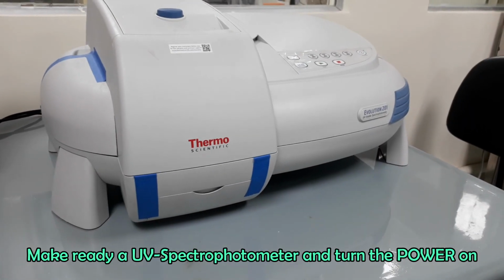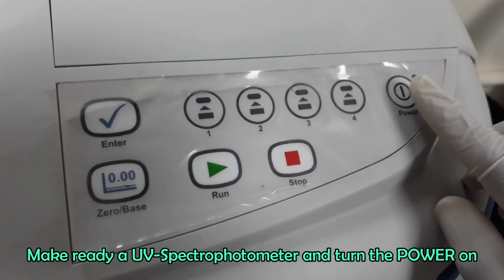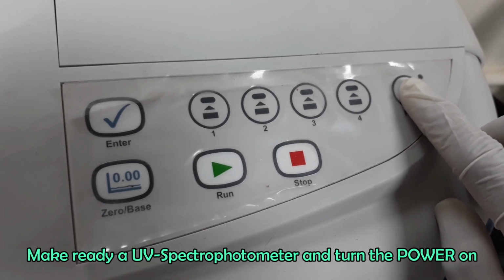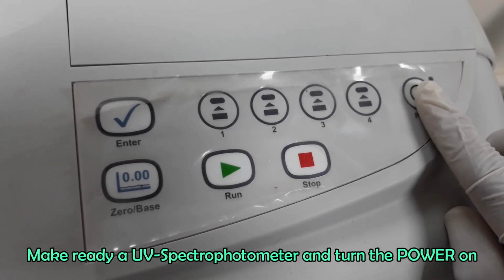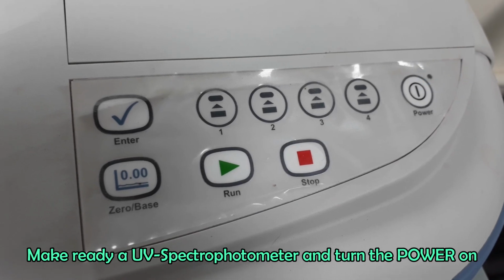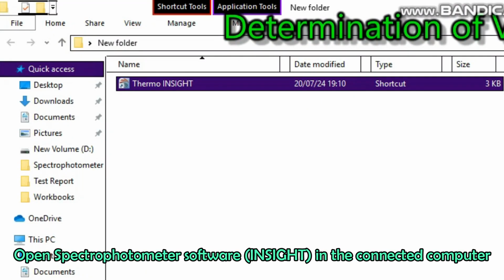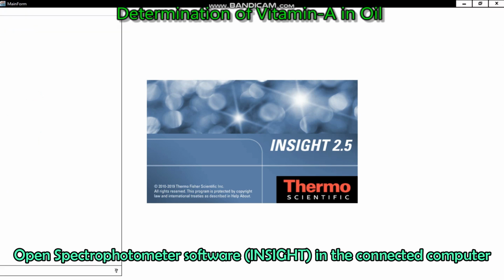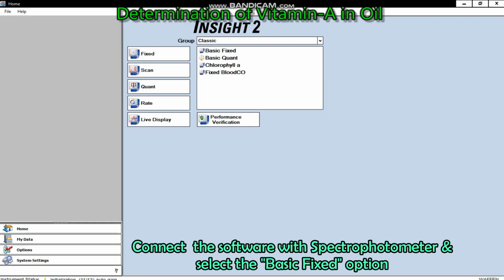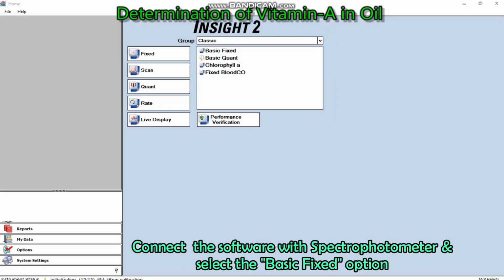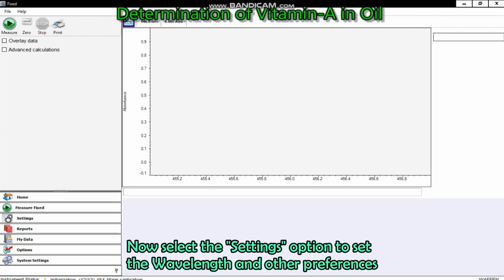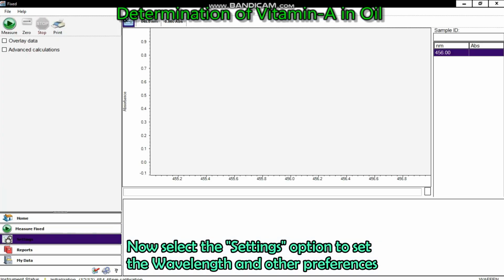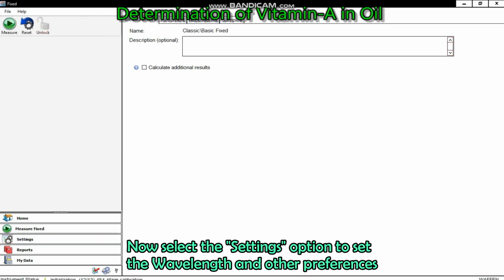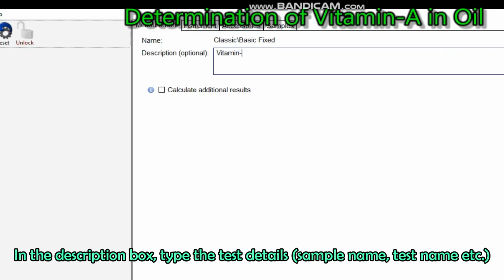Make ready a UV spectrophotometer and turn the power on. Open the spectrophotometer software in the connected computer. Connect the software with the spectrophotometer and select the basic fixed option. Now select the settings option to set the wavelength and other preference. In the description box, type the test details, for example, sample name, test name, etc.